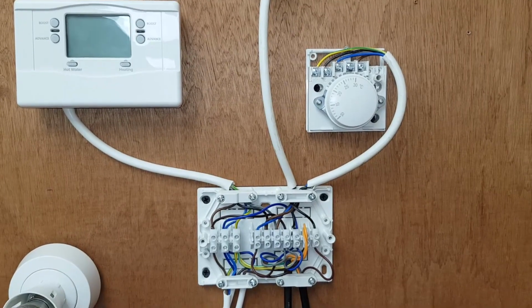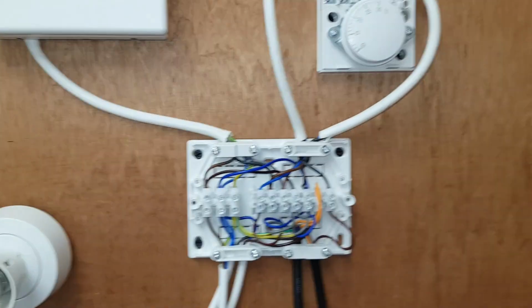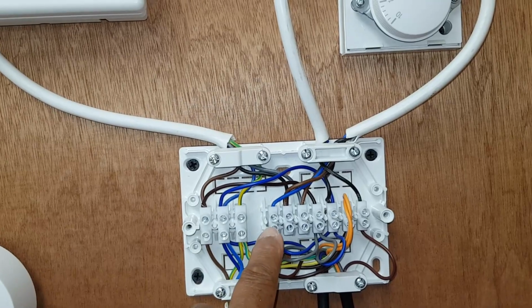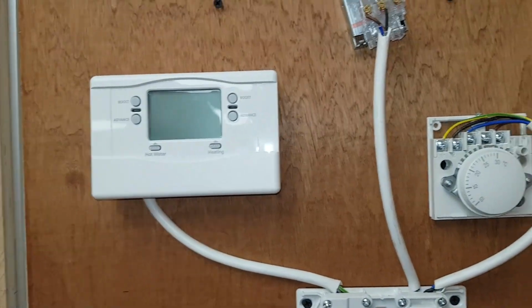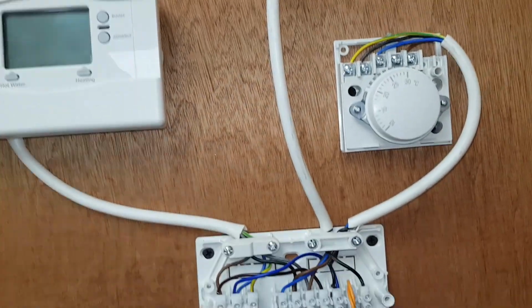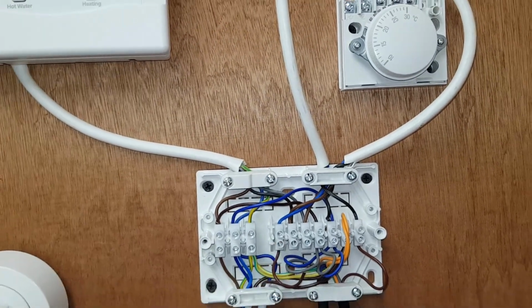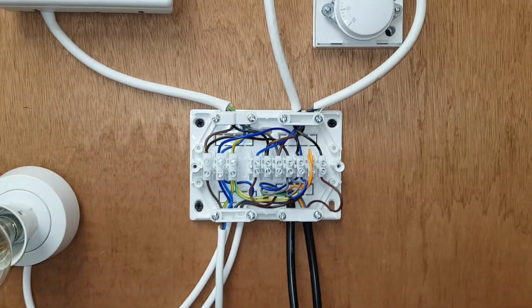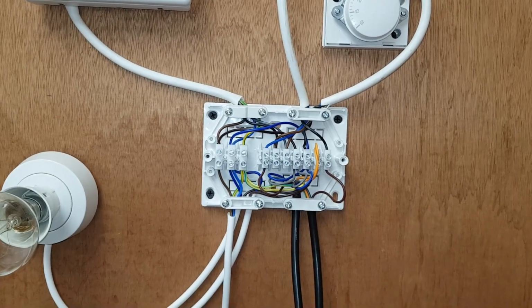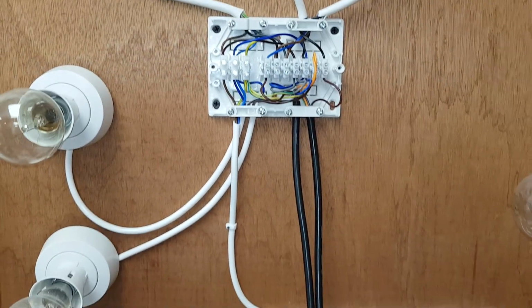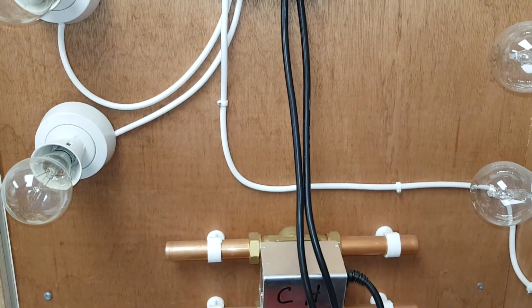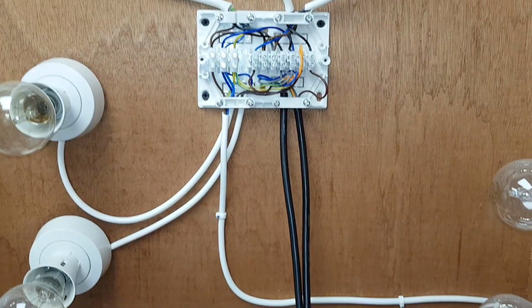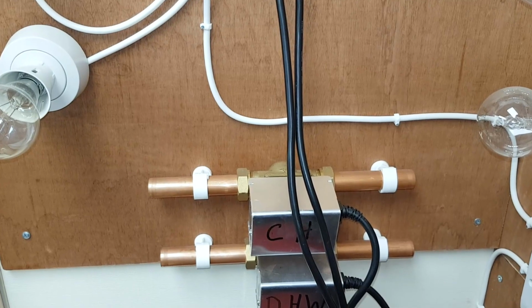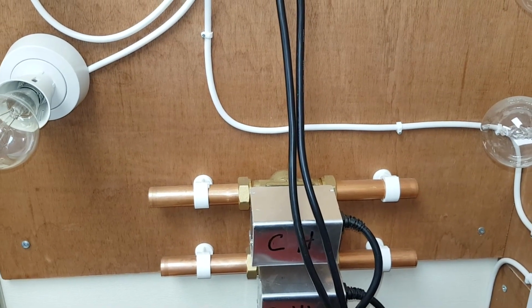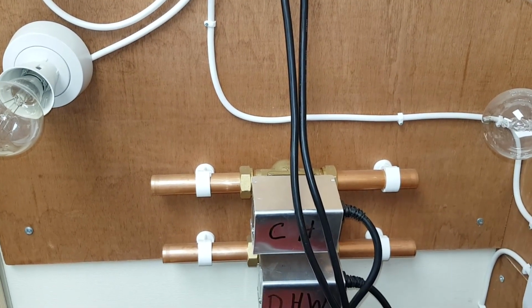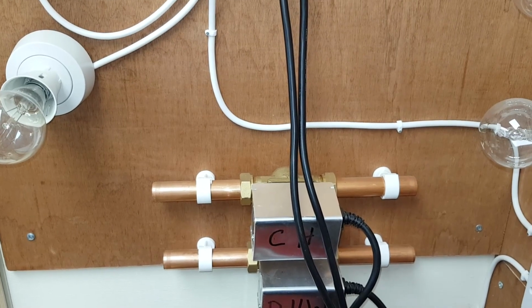Well done. Okay, another scenario. We have got power here, so that means your programmer and your room thermostat are working because we've got power here. Yet we've got no pump and boiler, no power on the orange. What would you be thinking then? Okay, so if you go back to that sequence, this brown comes down to the motor inside the zone valve, so perhaps the motor's failed. Okay. What else do you think could happen?